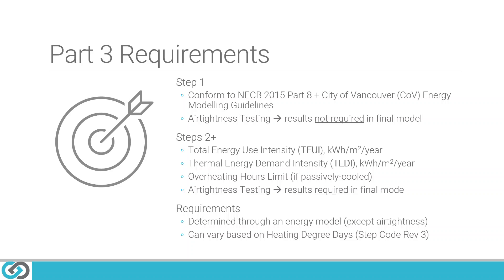All these requirements from Step 1 through Step 2+ are determined through an energy model, with the exception of airtightness, which is measured on site. It's also worth noting that the required value for a particular project can now vary based on heating degree days — this came out in the most recent Step Code revision, so we're flagging it to make sure it's on everyone's radar.